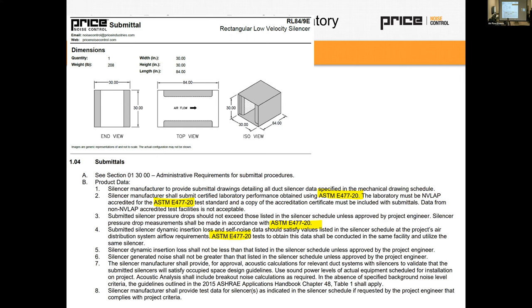Do you have to keep pressure drop down, or what's the reasoning behind it? Manufacturability is part of it. It's a little bit easier to put insulation on the vertical. The perforated metal that lines that baffle is easier reinforced when it's horizontal or vertical like that. When you put it on the top and bottom, you have the weight of gravity pulling down on it, and it could cause bowing. But that being said, we do often add insulation on the top where you have very high insertion loss requirements, like you need to absorb sound at a higher level. Adding perforated metal on the top portions as well and bottom can be an option. And we use that on our STC rated silencers.